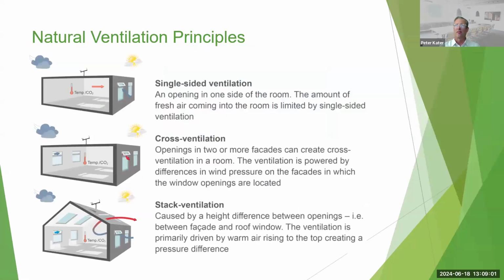The basic principles of natural ventilation include three primary types. There's single-sided ventilation. This is, I guess, the least useful because it limits the amount of air exchange with the exterior environment that can be achieved. Typically, it relies on having a window which opens at a higher level and allows air to be drawn out through the window, typically through a local stack effect.